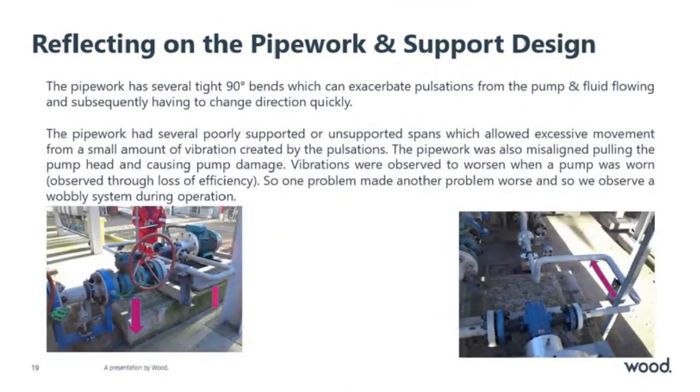Looking at the pipework support design, it did not really do very much to stop the movement, and it even exacerbated it by having a seesaw-like effect. So here you can see a center pivot point support and some big heavy valves on one side and the pipework unsupported on the other. A center pivot point, two heavy weights either side, and a constant input of vibration energy.